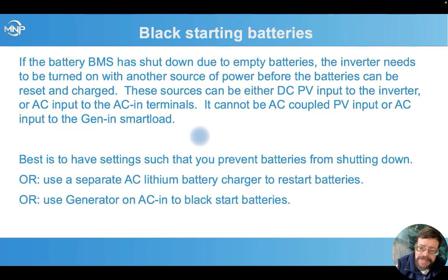So there are two sources other than the battery that can turn the inverter on and start charging that battery to get it restarted. This is either the DC PV input to the inverter. So if the sun comes out on our PV array, it'll become live from that source, or AC power to the AC in terminals of the inverter. We can't fire up the inverter's brain and get it going from AC coupled PV or from AC input on the generator in smart load. And that's because those are both controlled with relays that don't turn on until the inverter's up and running.